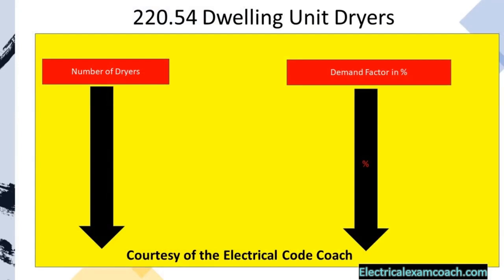When we get to Table 220.54, we're always going to read the black bold heading to make sure we're in the right table. We start on the left-hand side and find our number of dryers, then use a straight edge and come over to find our demand factor in percentage. You have to be very careful with these titles: sometimes they're listed as a replacement value and just say 'demand,' and in other tables it'll say 'demand factor in percentage,' which is just a multiplier.